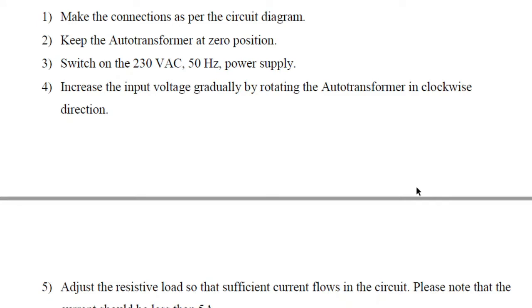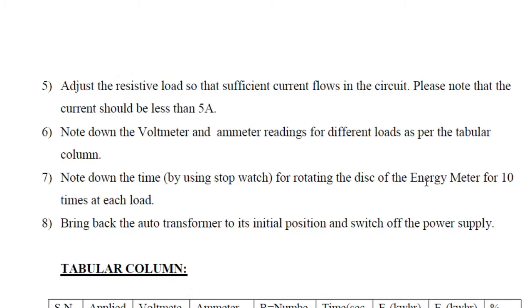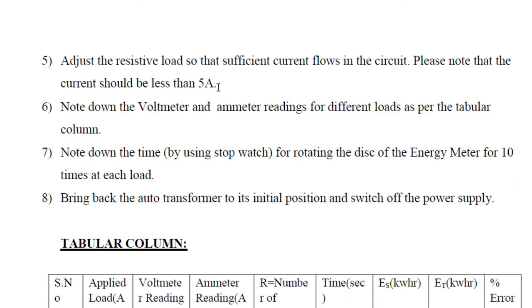Switch on the 230 volts AC supply, then increase the input voltage by rotating the auto transformer in the clockwise direction. Adjust the resistive load so that sufficient current flows in the circuit. Please note that the current should be less than 5 amps, because 5 amps is the maximum current allowed in the meter — exceeding 5 amps will damage the meter. Note down the voltmeter and ammeter readings for different loads as per the tabular column.